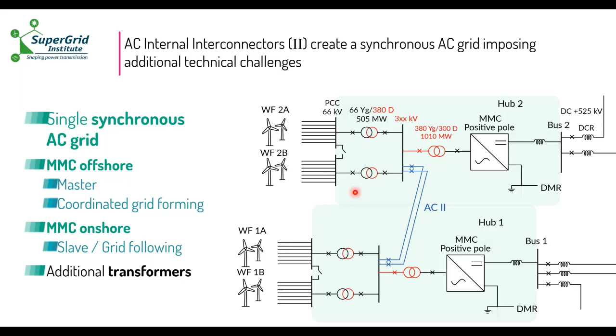Both solutions are compared in terms of capex first. In blue, the AC solution, and in red, the DC one. One of the main conclusions here is that the cable costs are actually negligible in comparison with the cost of the rest of the components in the DC bus. The difference here is mainly because you need a DCCB and a DC reactor in an offshore environment. That's why, in terms of capex, DC needs more investment to implement the solution. It starts becoming more interesting at the break-even distance of 20 kilometers.